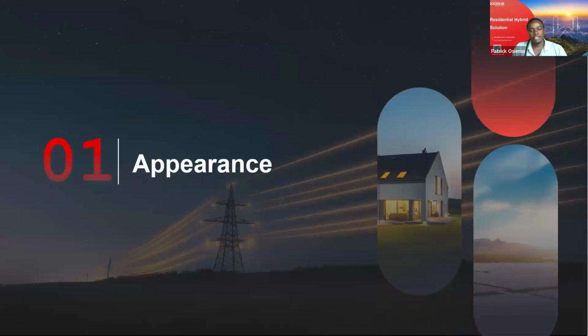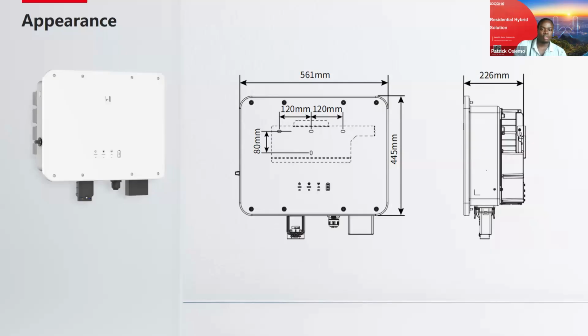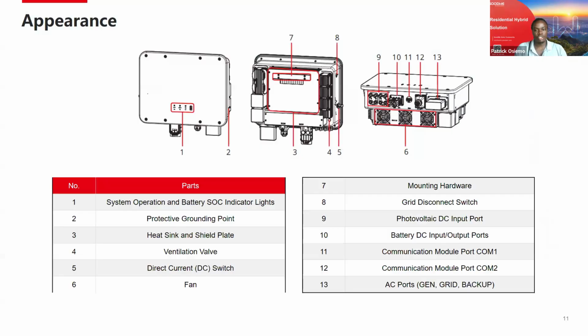Now, the appearance of the inverter: you'll see that it's quite compact. As you can see from the dimensions, it's easy to mount, with less drilling on the walls. We only have 4 holes to drill, and the mounting plate will be set to hold the inverter. Quite compact, quite elegant looking, and very easy to locate a mounting position for this inverter in the residence. Interaction-wise, the front has LEDs to show the status of the battery and the status of the inverter. And at the back are the mounting brackets and the heat sinks for cooling the inverter.